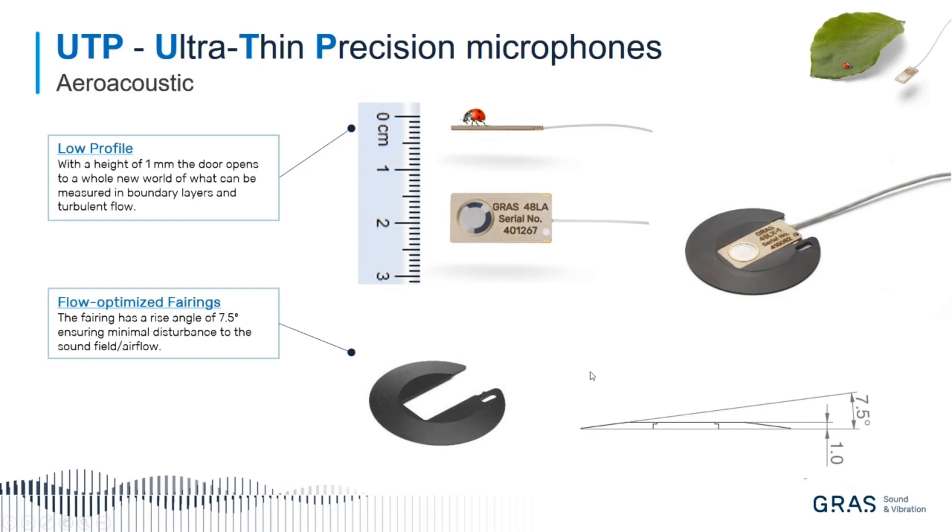On the surface, what you do is take a double-sided tape and tape it to the surface, then use this slot here to slide in the sensor. It goes into a locking mechanism and then it is locked in the holder, and you can do the measurement.